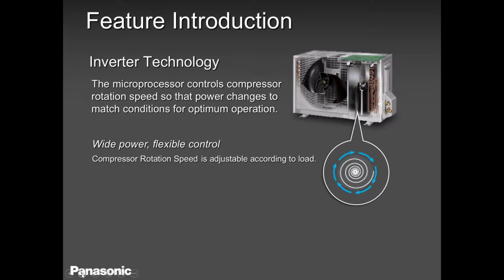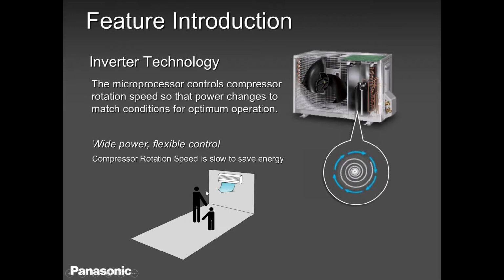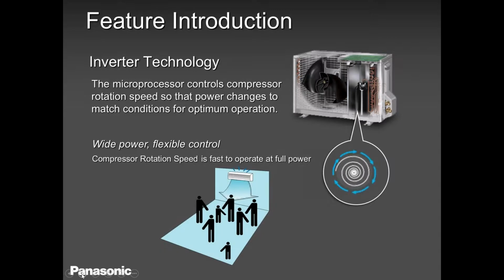So inverter technology, all our units, all our models that we are selling right now are all inverter technology. They are all IPM driven units. The compressors ramp up and down depending on the load. And as you can see here, the load is very little and the compressor is hardly running. And as the load increases, see what happens. The compressor ramps up. And who tells the compressor to ramp up? It's the indoor sensors. These indoor sensors here pick up this load, send the signal to the outdoor unit, and that's when the compressor ramps up or down depending on the room temperature.